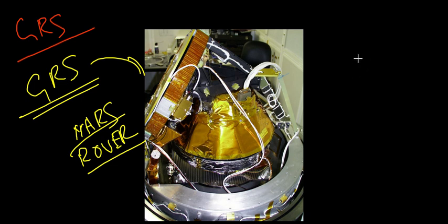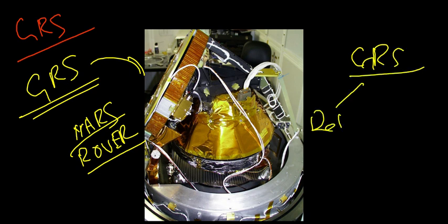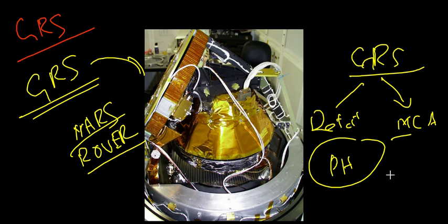Essentially, a gamma ray spectrometer has two main parts. One is the detector, followed by the multi-channel analyzer, which classifies the different pulse heights. Why are we bothered about the pulse height? Because pulse height gives you information about the energy of the radiation. The energy of the radiation identifies the particular nucleus which emitted it. Thereby, you will be able to analyze different substances that emit gamma rays.